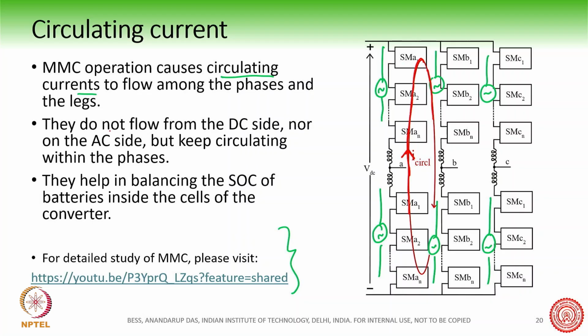Why is this called a circulating current? Because this current does not flow from the DC or AC side, but keeps circulating within the phases. Because this circulating current is flowing, you can use it to adjust or balance the state of charge of the batteries. SOC is an important parameter that must be maintained for all the batteries, ideally at the same level all the time, otherwise one battery will discharge more than the other. With the help of this circulating current, it is possible to balance the SOC of the batteries.